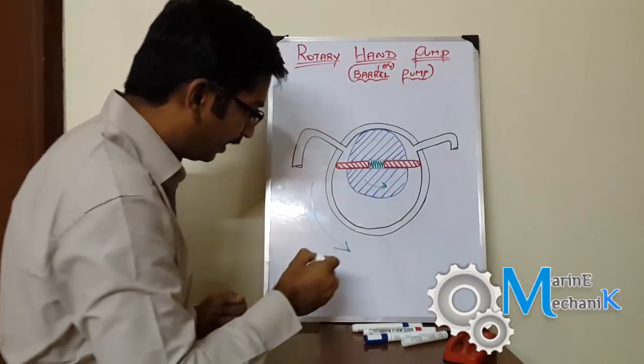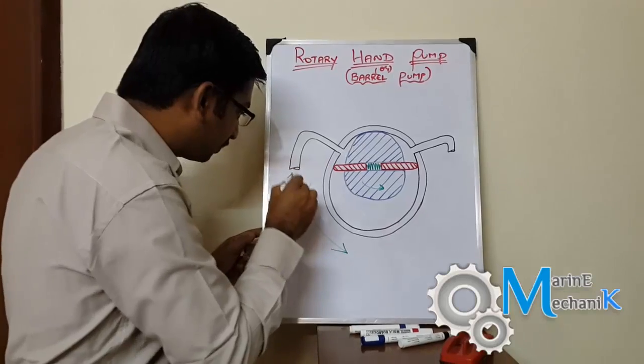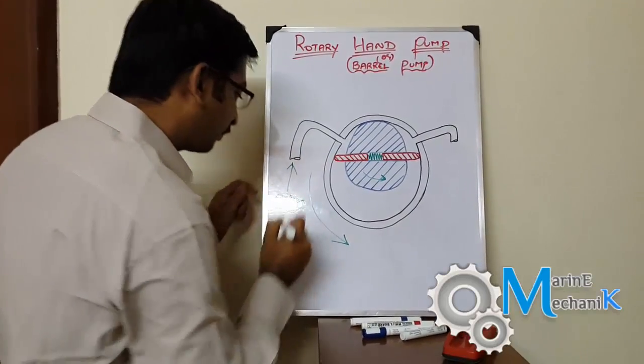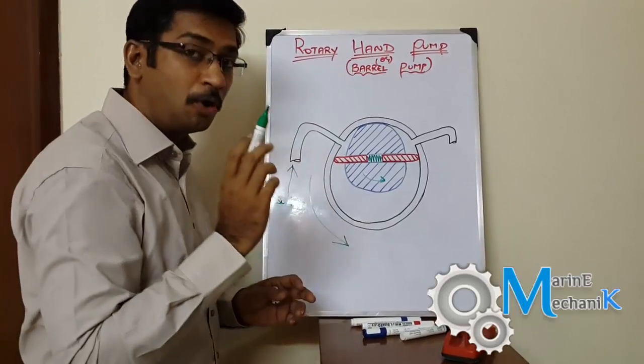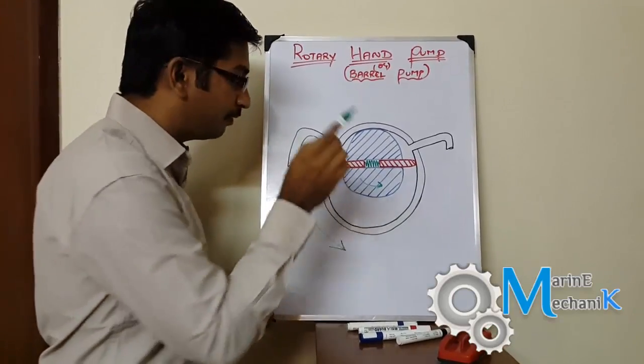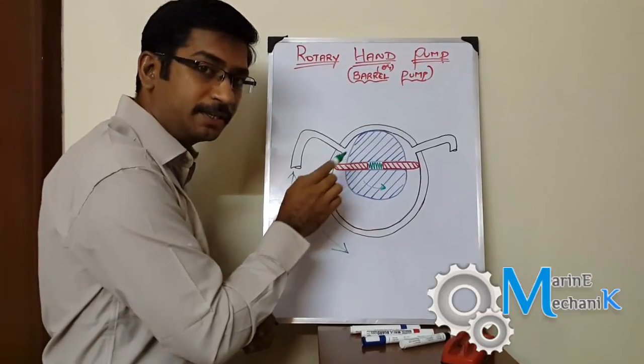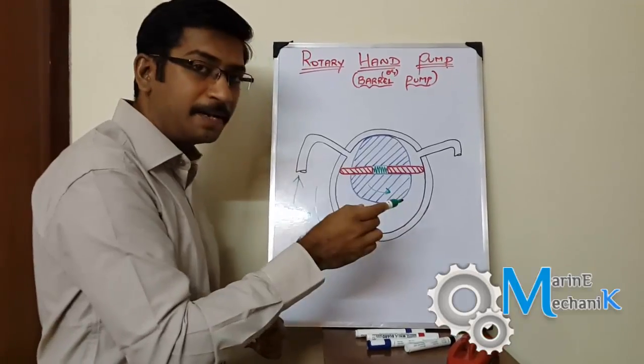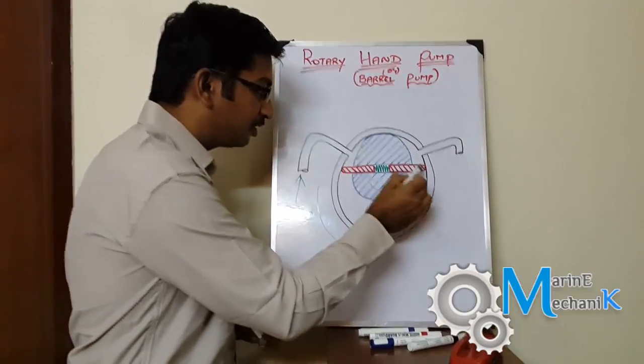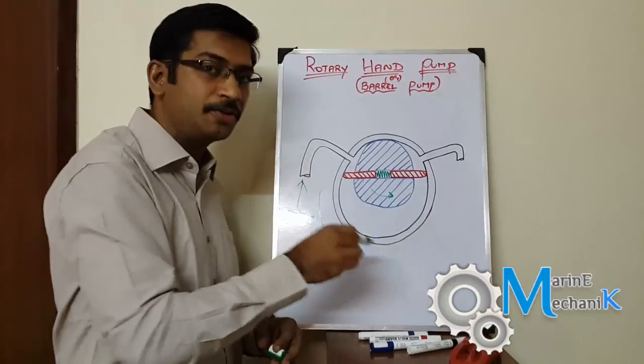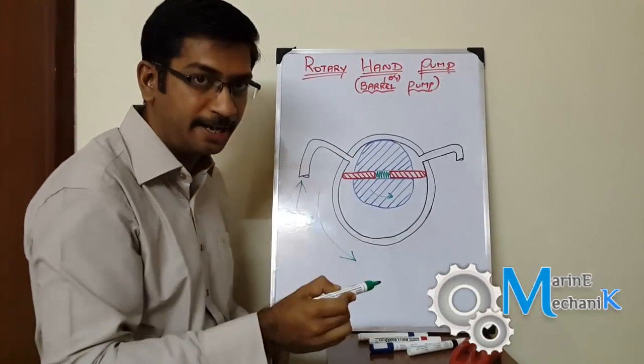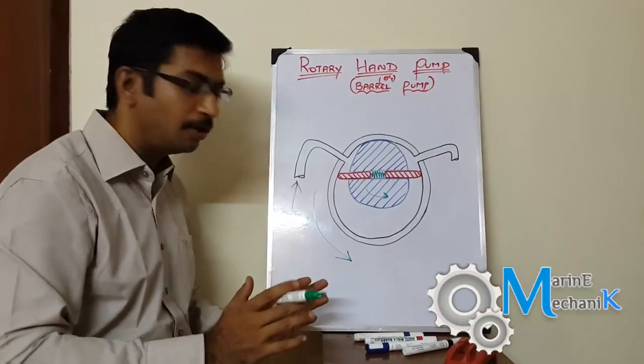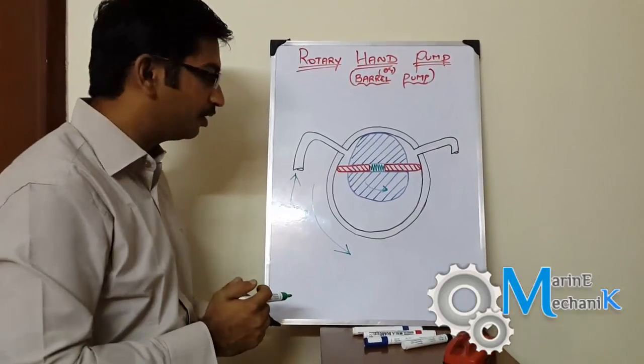When you rotate it anti-clockwise, this is going to rotate in anti-clockwise direction, and assuming this to be the suction. You have to remember that we are not going to use this pump for air or any gas on board ship, because for that application you need special seals. But on board ship, what we use is a simple pump just to pump oil or sludge or even sometimes fresh water.